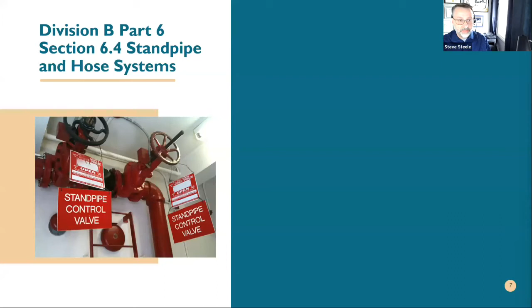So again, I just kind of broke it down in comparison. We have Division B, Part 6, 6.4. It basically deals with your standpipe and hose systems. So I'll first touch on what's required, or what, this is a small little piece of what NFPA 25 does. If you look at Chapter 6 in NFPA 25, it gives you the bare minimum requirements, and you'll see obviously that minimum or expectation is a little bit more than what's in OFC.